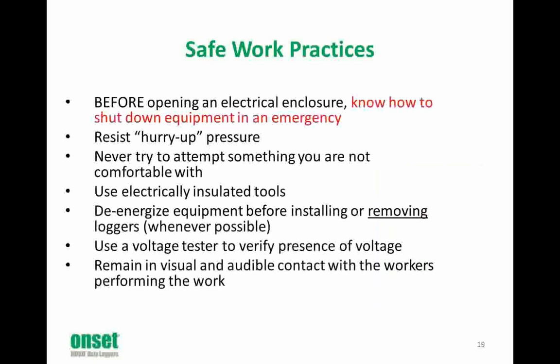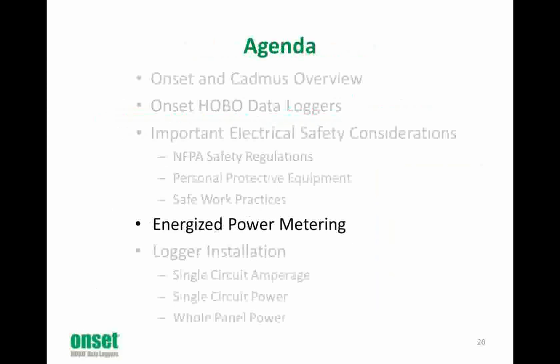Again, I say whenever possible because sometimes we'll need to do an energized voltage test. We'll want to use a voltage tester to verify the presence of voltage. I'll discuss voltage testing a little bit later on. And we'll also want to remain in visual and audible contact with workers performing the work. So it's good to work in pairs or in small groups whenever possible. And now we'll get into energized power metering.